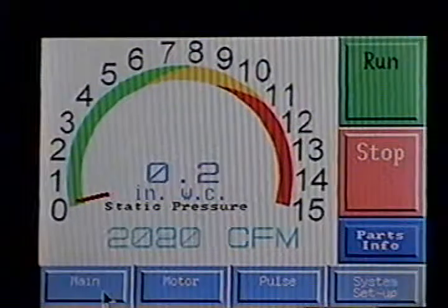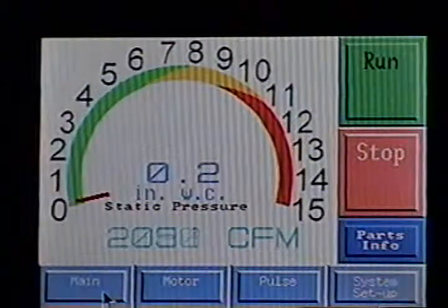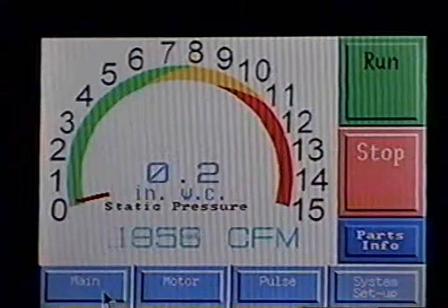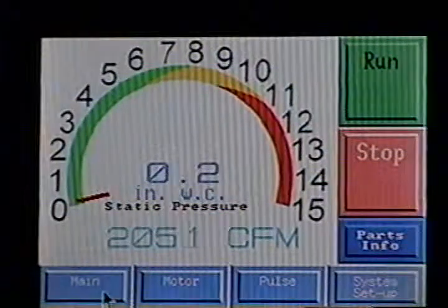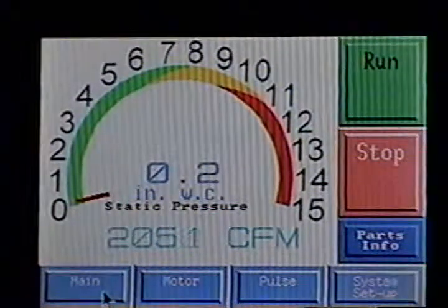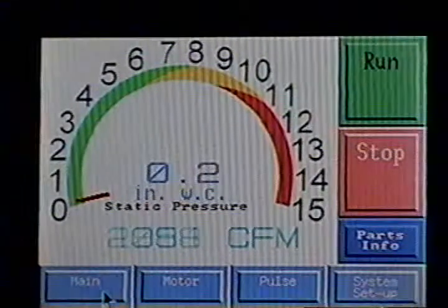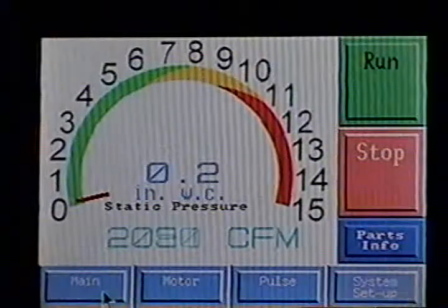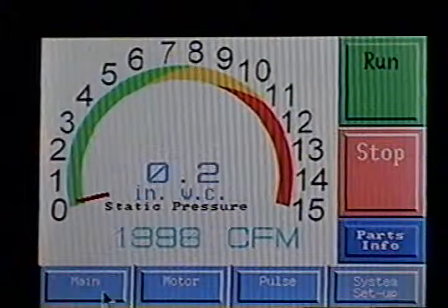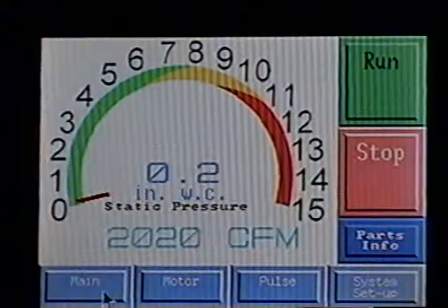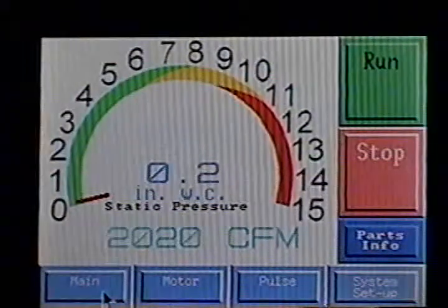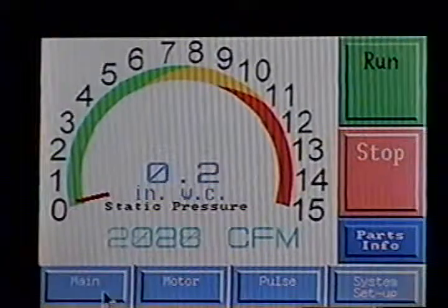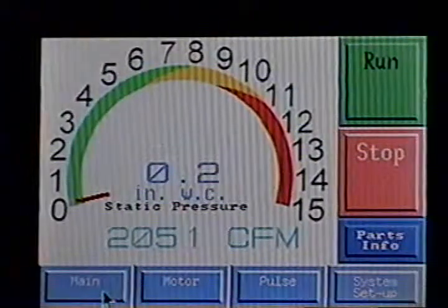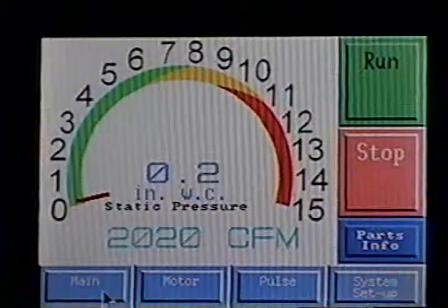That allows us to go through and use the same system for a 5 horse, 10 horse, 7.5 horse, custom 7.5 horse, 15 horse, 20 horse, 25 horse, 30 horse. It doesn't matter what blower it is, or if the blower is spec'd out for higher static, lower static, that blower can change. We don't care. We're measuring the airflow through the ductwork. And you can see it back there.